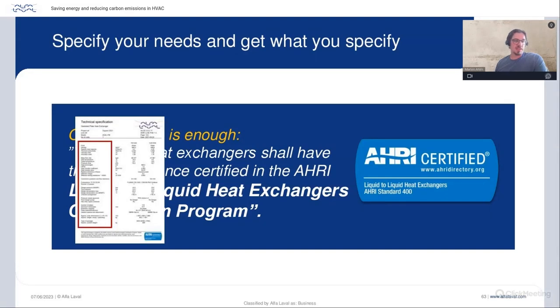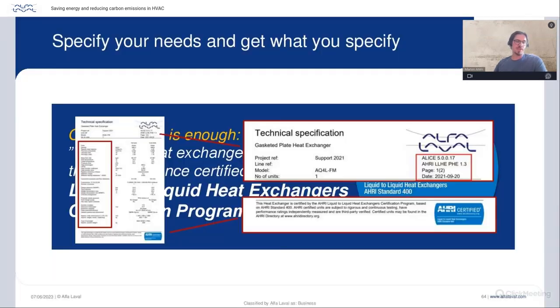The additional value is that if we compare a technical specification that is certified, you will get much more data than what you get in a usual tech spec. This is also demanded by the certification program, to ensure that you hand out all details of your product. And it should also be traceable. You should be able to see the software version and when it was made, and there should always be the disclaimer with the AHRI certified logo on the tech spec. This is how you can determine that you have received a certified design that is surveilled by this third party.